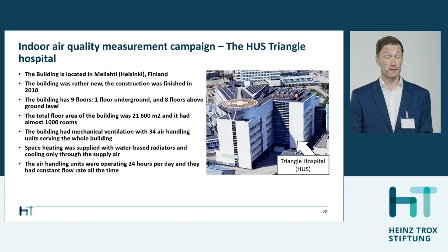The building had mechanical ventilation with 34 air handling units in total, servicing the whole building. Space heating was supplied with water-based radiators, and cooling was supplied only through supply air. The air handling units were operating 24 hours per day with a constant flow rate the whole time.